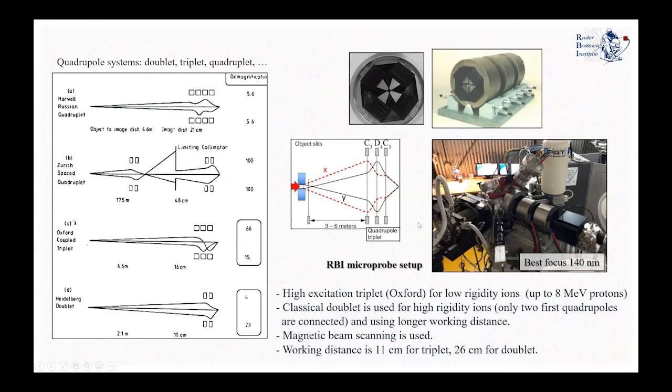You can see on this sketch on the right how the setup looks from above. The three quadrupoles are positioned on a holder which allows micrometer precision positioning of each quadrupole in X, Y, and Z, as well as tilt of each quadrupole, which is important to properly align each of them. We also use a magnetic scanner to move the beam when it's focused.